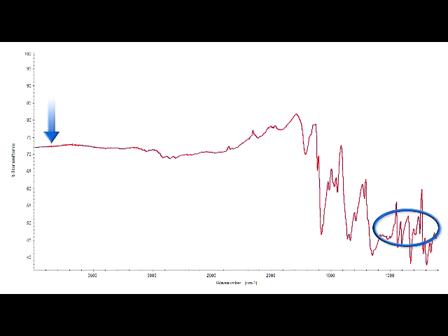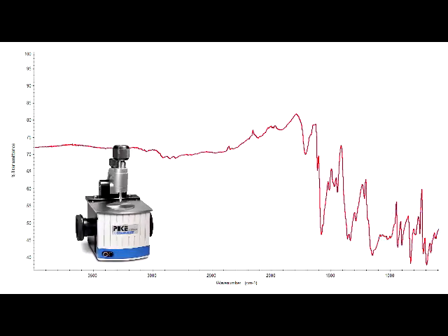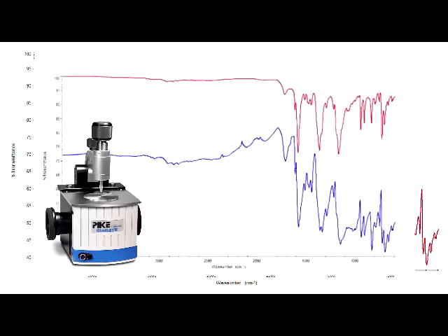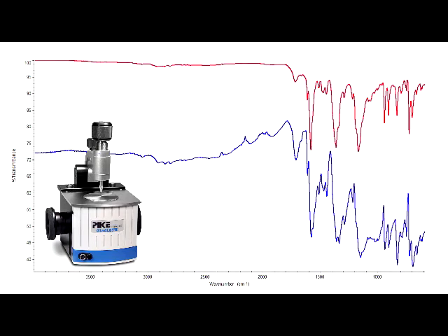One option to satisfy the critical angle would be to take advantage of the GladiATR's interchangeable plates and switch to a Germanium ATR crystal. Then the critical angle is satisfied.